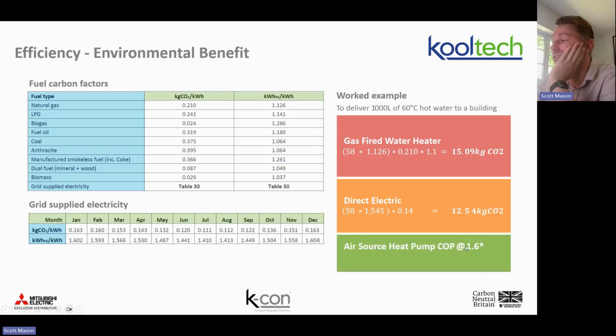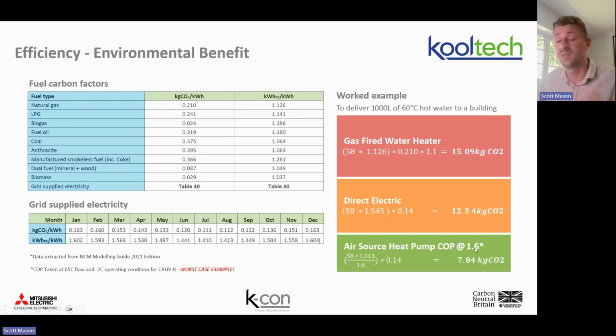And then if we look at an air source heat pump, now I've taken a coefficient of performance, a COP of 1.6. Now the reason I've taken 1.6 is because that's what the unit, the CAHVR efficiency will be at an outside air temperature of -2 degrees centigrade and a flow temperature of 65. So it's potable hot water. We need to store it over 60. So realistically, I need to deliver 65 because there's going to be a plate heat exchanger or a coil or something in there for our heat transfer.